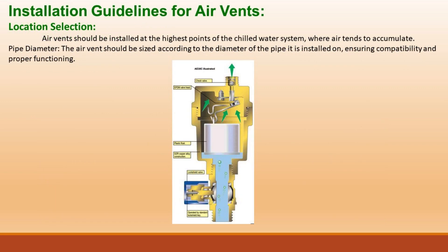Installation guidelines for air vents. Location selection: air vents should be installed at the highest points of the chilled water system, where air tends to accumulate. Pipe diameter: the air vent should be sized according to the diameter of the pipe it is installed on, ensuring compatibility and proper functioning.